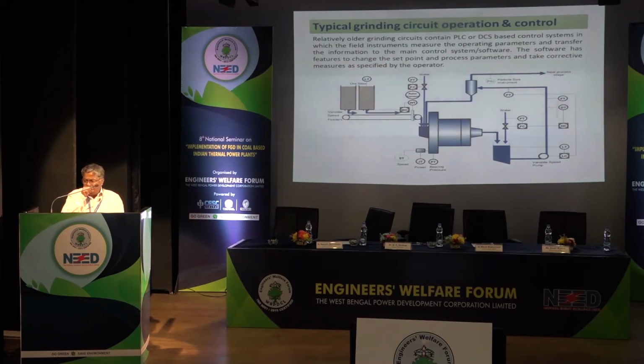Next important is pH control. You should be very clear that it is alkaline. There is no chance that it should be left for even a little bit being acidic. It must be strongly alkaline. So pH control you can do here itself, or you can do separately for the water, because you are already using in power plant a huge water supply system and recovery system. So there also you can do. But one thing to be clear is that water supplied to FGD system for grinding purpose has neutral pH. Sorry, not alkaline, neutral pH.